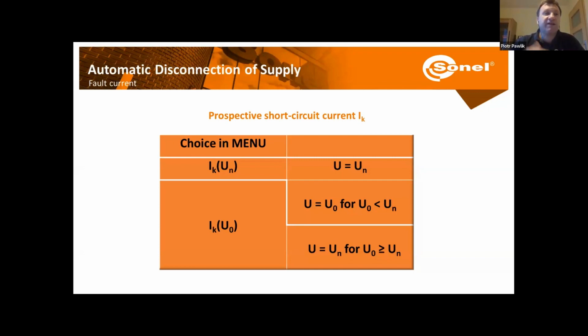So here we're going to select the lower one, because that will give us, as the result of the calculation, a lower value of the fault current, and therefore our conditions will be more strict. So let's say in case we are somewhere close to the transformer, and the value of voltage in the socket will be 240 volts, then we're going to select for the calculation the nominal value, which is 230. On the other hand, when we are far away from the transformer and the measured value of voltage in the socket will be about 220 volts, then we need to use this actual measured value.